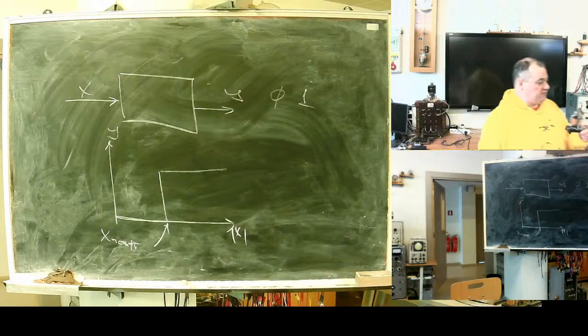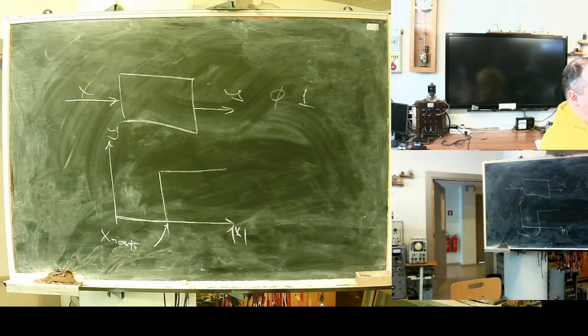A bit more modern design, it's a voltage relay. Coils, anchor, and contacts to give out open and close signals. And how is the trip point set? With the spring, I have a lever, I can select 40, 50, 60, 70, 80, or also a factor of 2 can be employed. For example, I'll set this and multiply by 2, it will trip at 100 volts.